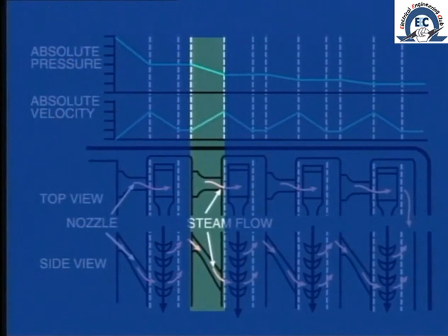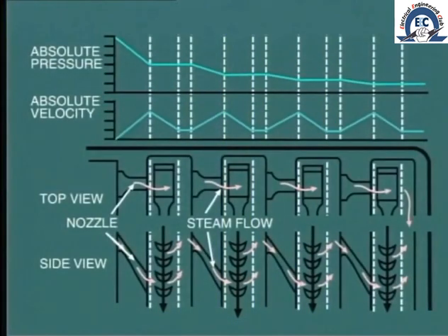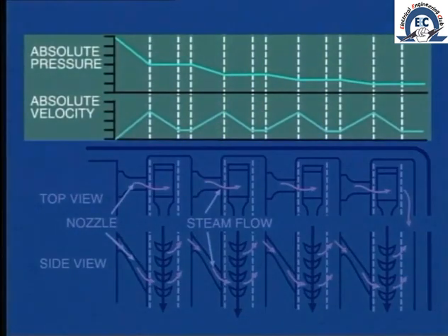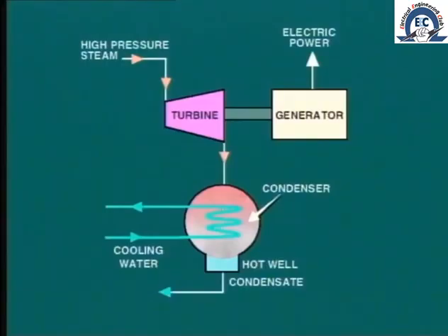Again, the pressure falls and the velocity increases due to expansion of the steam, and once again this is directed onto the next row of moving blades and so on. We can see that as a result of pressure drop, the velocity of the steam increases each time it passes through a set of stationary blades, but the velocity then decreases as the steam passes through the moving blades and gives up energy. Eventually, when the pressure has fallen to a low value, it can no longer expand and produce work and it is exhausted from the turbine.